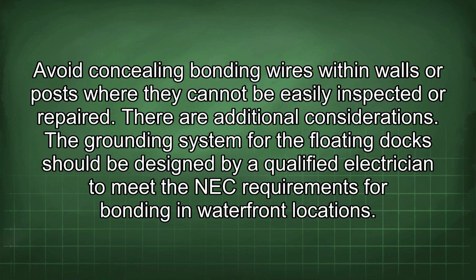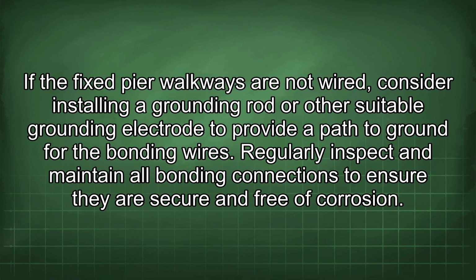There are additional considerations. The grounding system for the floating dock should be designed by a qualified electrician to meet the NEC requirements for bonding in waterfront locations. If the fixed pier walkways are not wired, consider installing a grounding rod or other suitable grounding electrode to provide a path to ground for the bonding wires. Regularly inspect and maintain all bonding connections to ensure they are secure and free of corrosion.